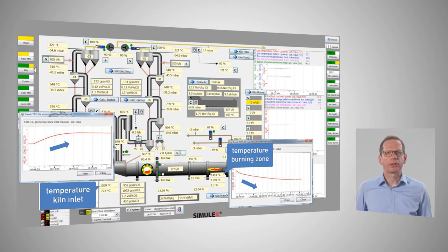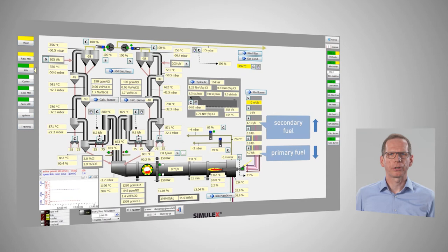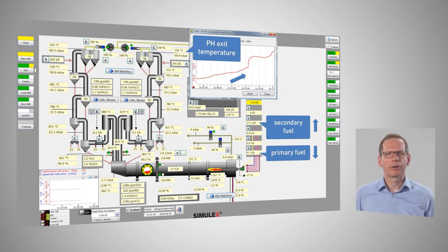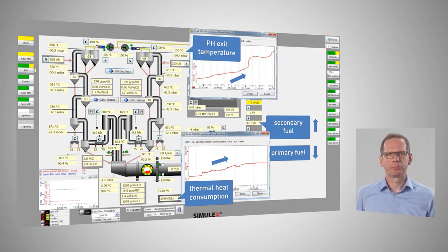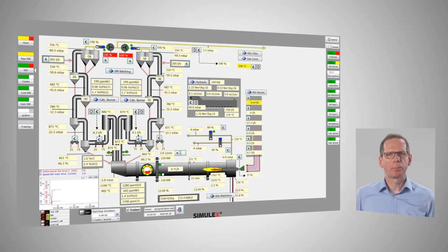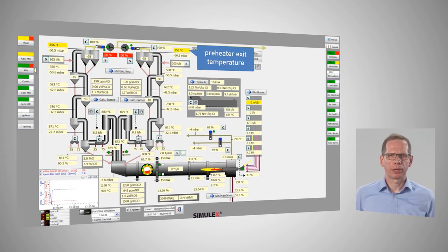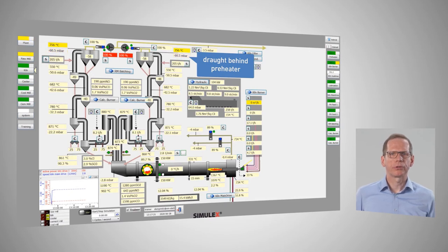Let us continue to simulate our initial scenario by supplying even more alternative fuel to the main burner. To maintain proper burning conditions we must now consider ID fan speed and preheater exit temperature. As we can see, the overall thermal losses — respectively the specific heat consumption — are now significantly elevated. Continuing our approach to replace even more coal dust by secondary fuel, we are about to reach the theoretical limit of this example scenario. The ID fan is running at maximum possible speed, exit air losses at the preheater have further increased, pressure losses across the entire pyro process are significantly higher, the condition in our burning zone is poor, and we have just very little excess air left in our inlet chamber.